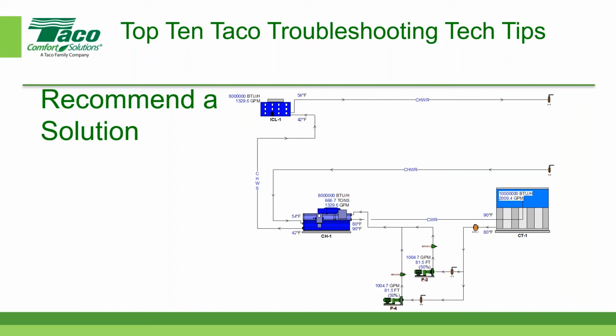So Mike says, would an oversized strainer solve the issue, or do you even need the strainer? You know, that's some decisions you've got to make. Right, and this was a real situation, by the way. I changed the numbers a little bit to make it easier to read, but this came up about 3 months ago, and it turned out it was in fact the basket strainer. At that point, I ended the conversation with the owner, and I basically just said, look, it's clear that the basket strainer is the problem. It's up to you to work with the basket strainer supplier. We didn't provide the basket strainer. It was not provided by our rep on the project. They bought it from someone else. And so we just narrowed down what the issue was to the component and then let them figure out what to do with it.